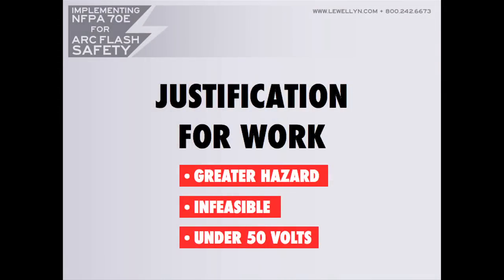Anybody here work at the airport? How about a hospital, got somebody there? You folks can maybe use greater hazard as an excuse somewhere. If you work at a hotel, you might be able to. Like in this hotel, if you have to work on the fire pump circuit, we don't shut fire pumps off in the middle of the night. We don't shut off fire systems because we want to work de-energized. Those things are hooked directly to God. We don't shut those off for anything.